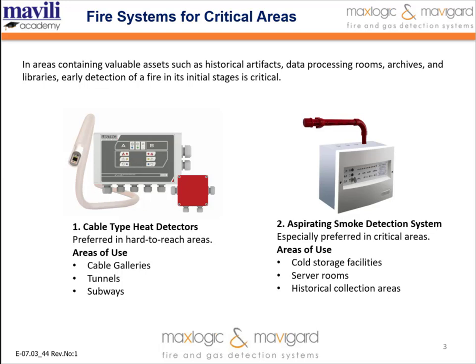First of all, aspirating smoke detection systems. This is one of the most preferred solutions in critical areas. It continuously draws the ambient air through the piping system, the holes into the device, and analyzes it very precisely. So it is used especially for early smoke detection in data centers, server rooms, telecommunication rooms, archives, libraries, museums, and such places containing highly valuable equipment and assets.